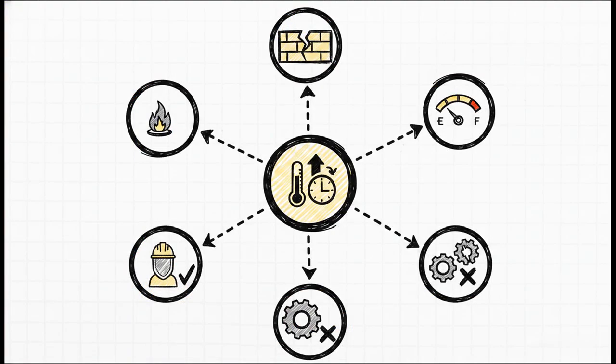I mean, really think about it. If that furnace heats up way too fast, those expensive refractory bricks could crack. That's a huge safety problem, not to mention a disaster for the budget. That's material integrity. If it heats up too slowly, you're just burning fuel and wasting money. That's an efficiency problem. And if you're trying to treat a piece of metal in there, the rate of heating completely changes the quality of your final product. So this one little number, it actually affects everything.